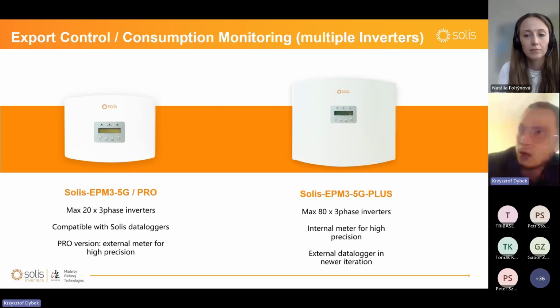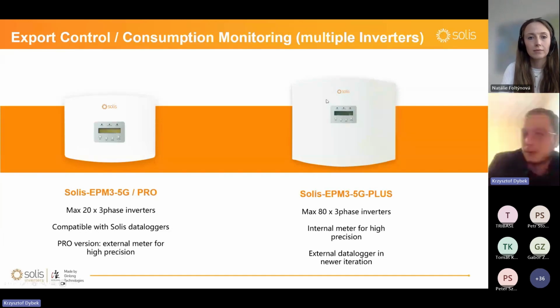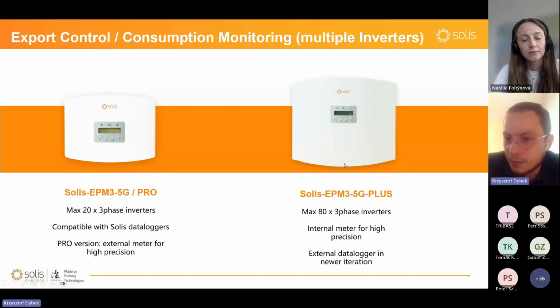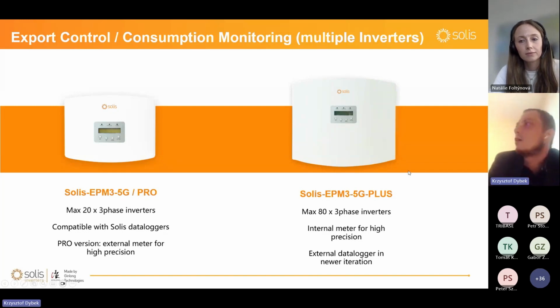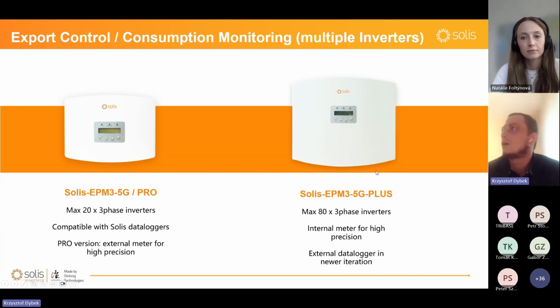And about differences between those two models, Solis EPM3-5G-PLUS, this is the bigger guy, used for 3-phase inverters up to 80K. Main difference is this EPM has built-in power meter here, let's say under the cover, and for highest possible precision, so need only current transformers to set it. Previously, we had also in this cover inside old Solarman dataloggers, but we got rid of it because yeah, we don't use Solarman anymore. So this guy most likely will come with just new dataloggers for our Solis Cloud, and can be inserted here. Let's see, but the meter is inside.